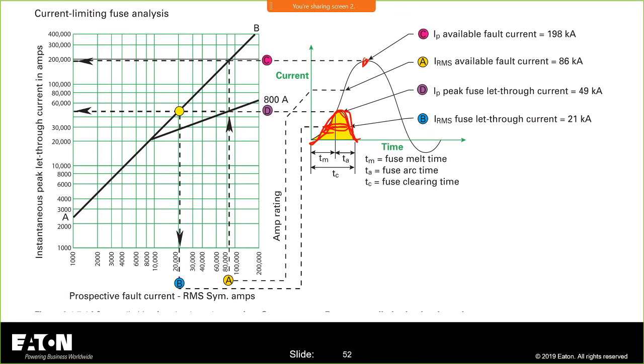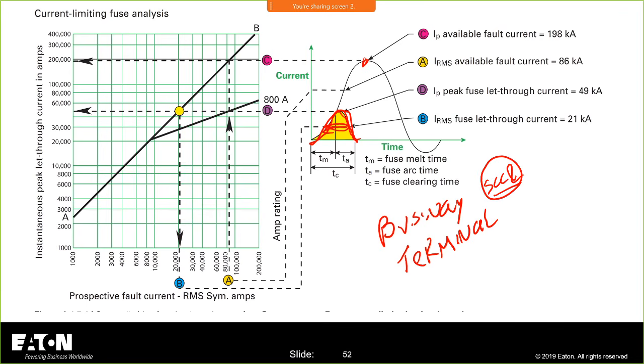And that gives me the new RMS value, which, if I have static equipment like busway, or a terminal block or a terminal strip, something that is not dynamic, that is not going to try to open the circuit, then I can compare this RMS value with the SCCR of that busway or that terminal. If it's 10K without a fuse, I need to make sure that my let through, this up, over, and down, gets me to a number less than 10K. If it's 22K, this number has to be less than 22K. I will do that comparison to make sure that I'm providing that level of protection as it's rated.